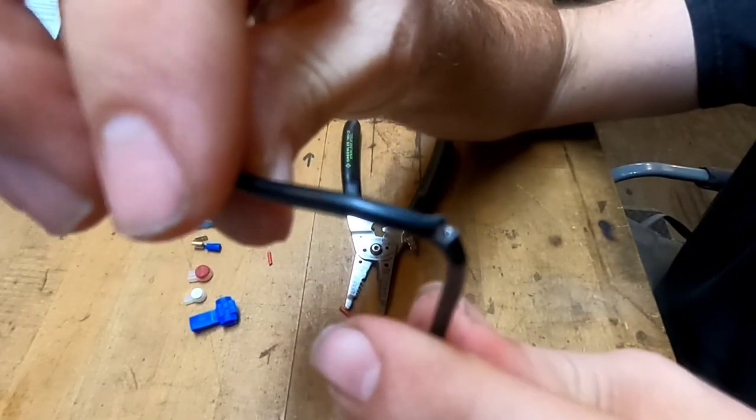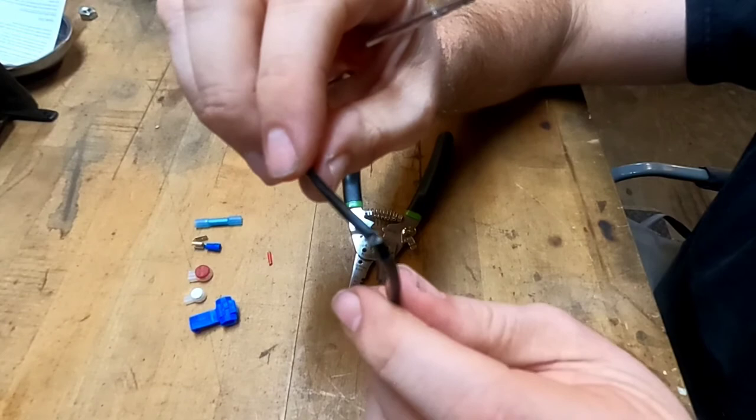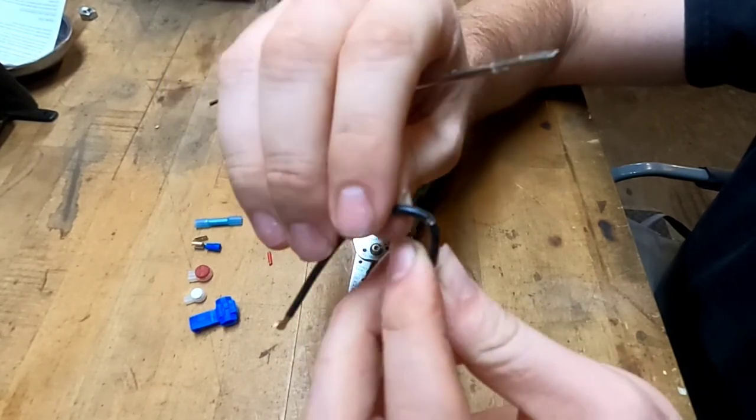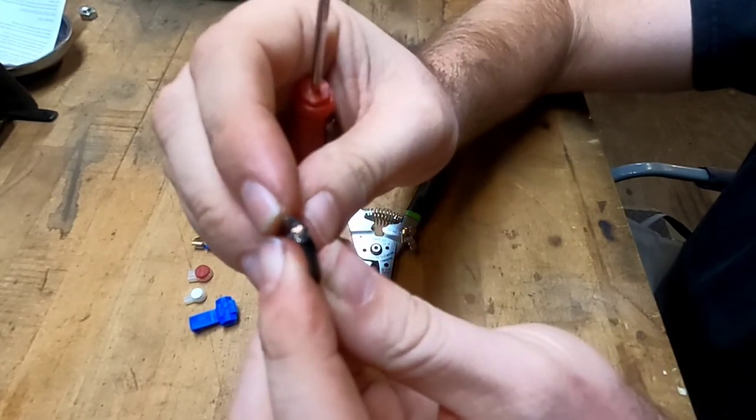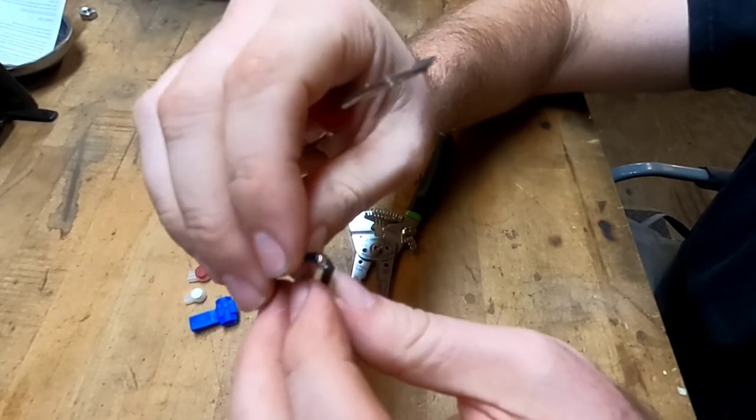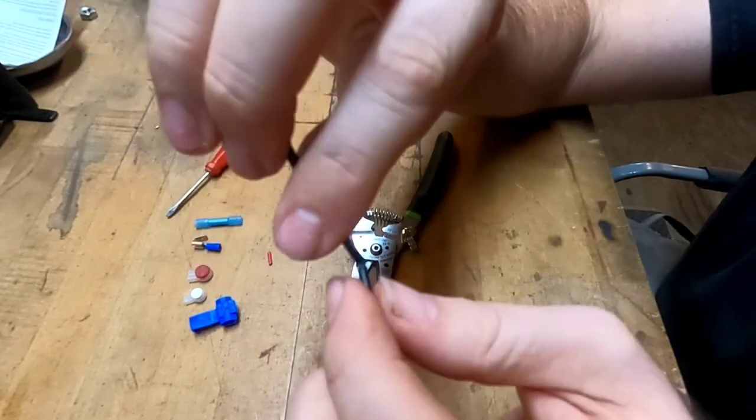So the black one, it did pierce the insulation and the conductor, but it also broke through some of the strands of conductor, which is not good, right? That actually increases the resistance in the circuit because we're losing strands to be able to pass current through this conductor, through this wire.